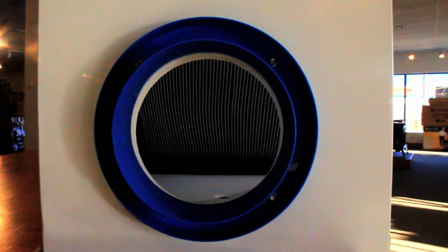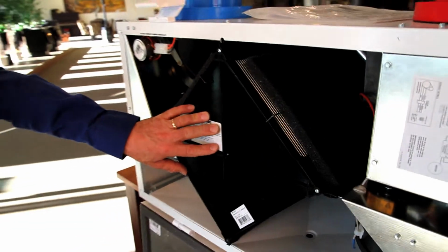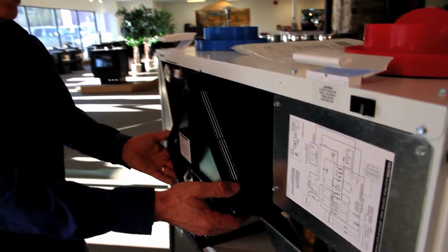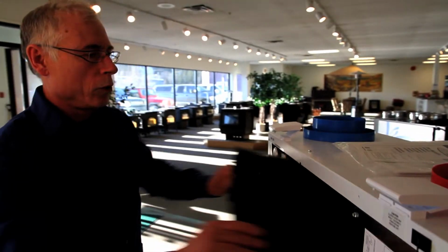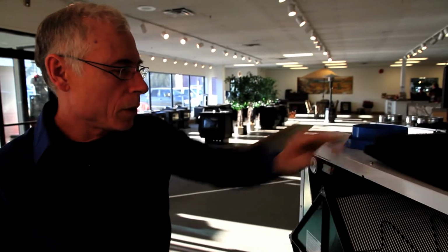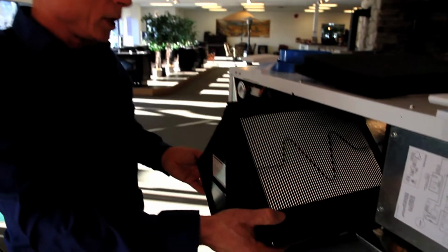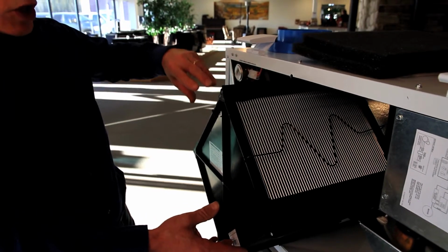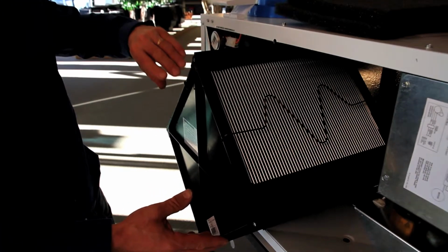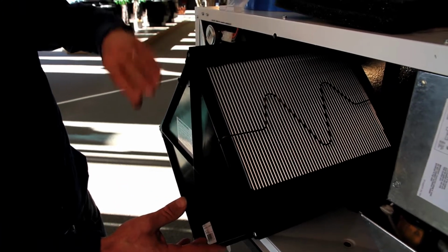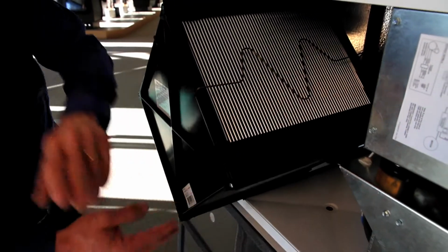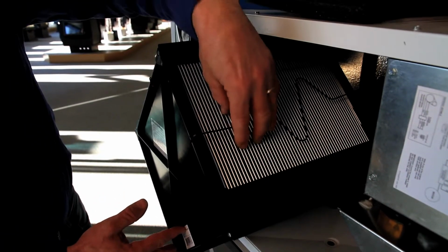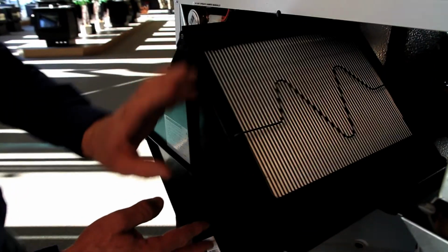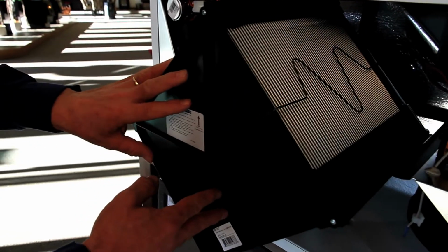So now we're looking at the heat exchanger, which is the core of the unit, and we're going to have a look at it here. I'll remove these air filters and explain later, but this is the core itself, and what we have is separate channels so you don't allow intermixing of air. You have your fresh air channel coming through here, and you have your exhaust channel, which allows the warm air to pass by the cold air and passively exchange the heat one to the other airflow.